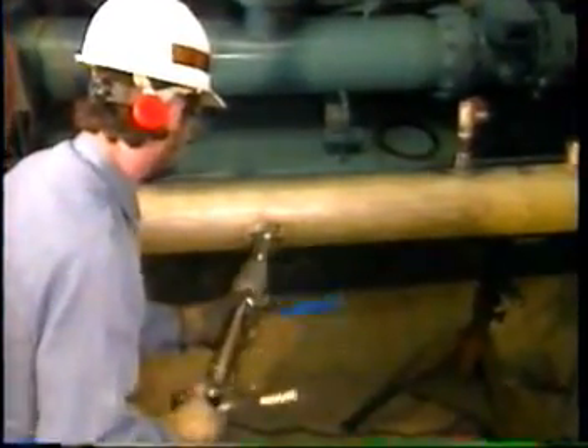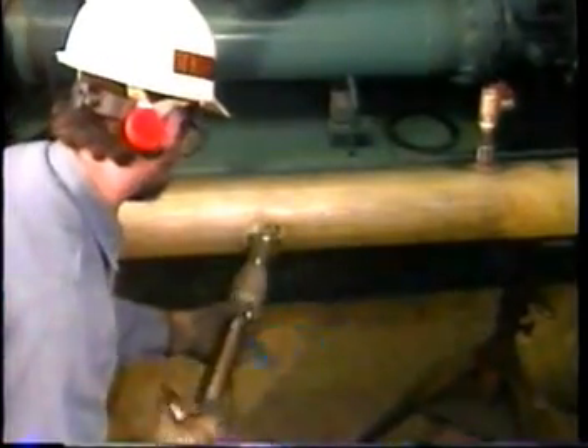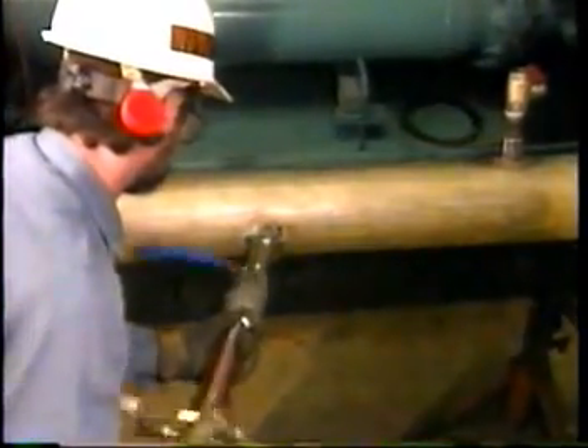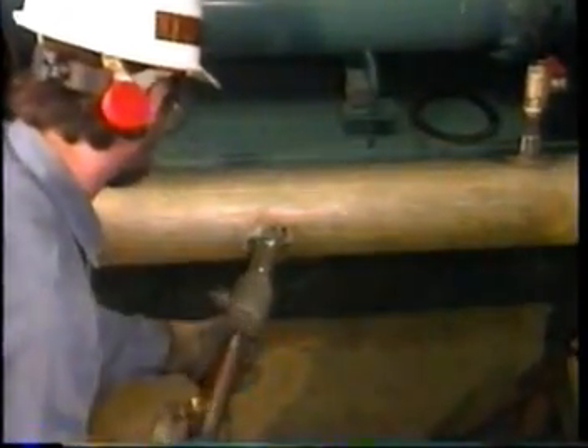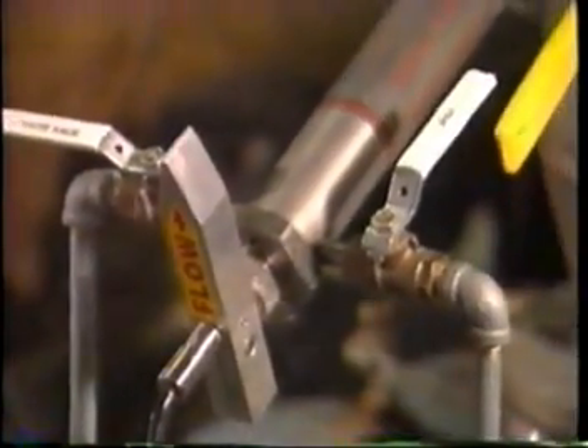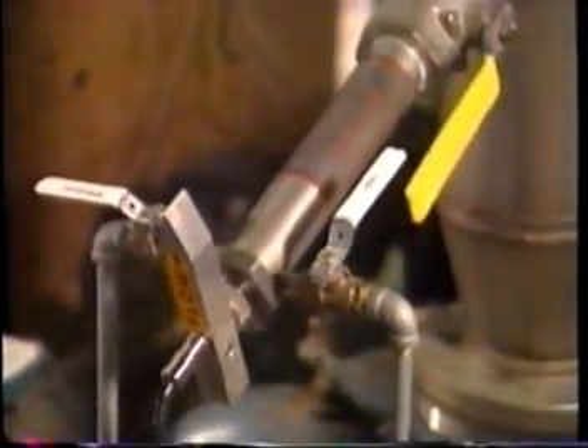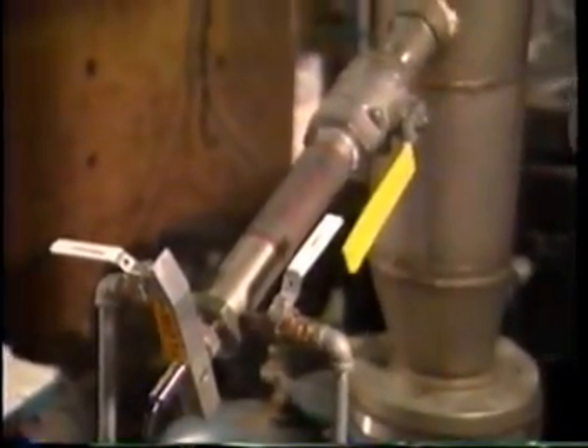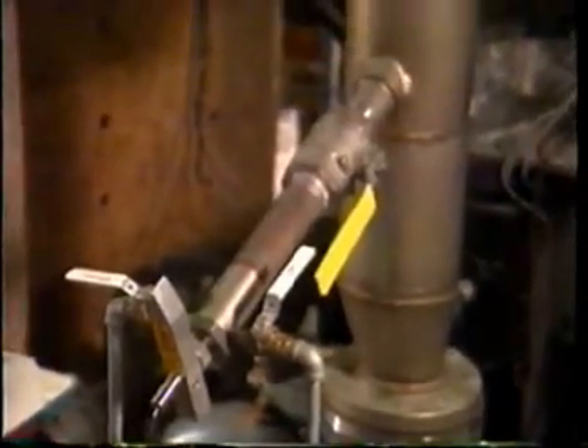If the chosen line is horizontal, be sure to insert the probe from the side, not the top or the bottom. If the chosen line is vertical, be sure the flow direction in that pipe is upward. It is nearly impossible to eliminate the formation of large void spaces as stock accelerates due to gravity when it's falling downward in a line.